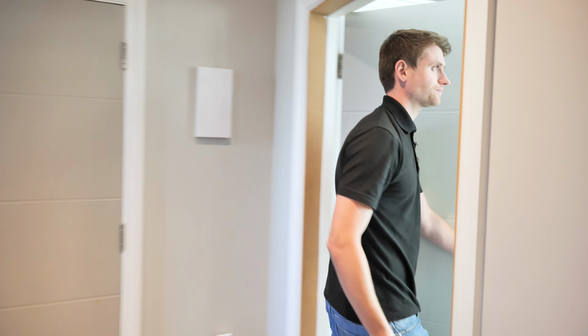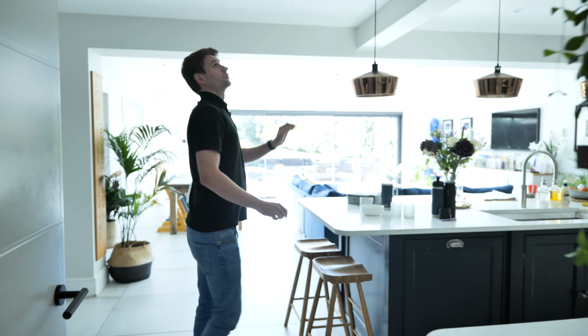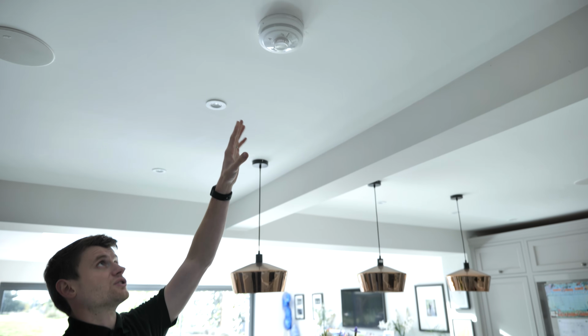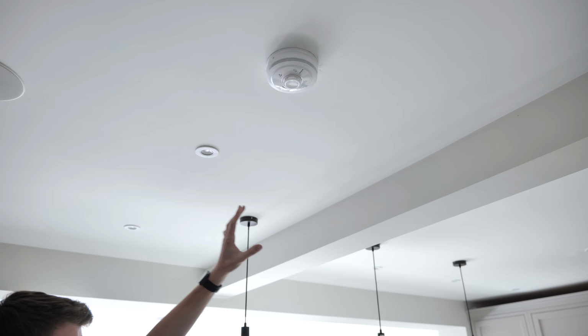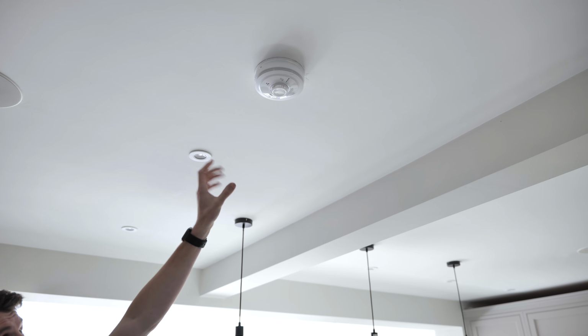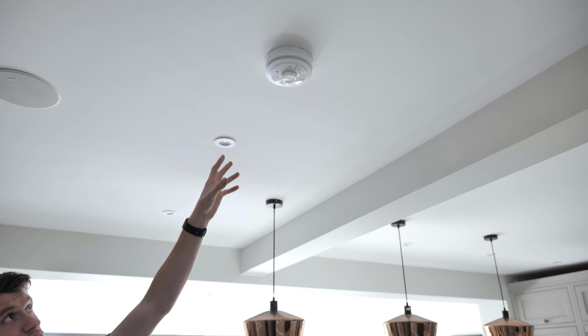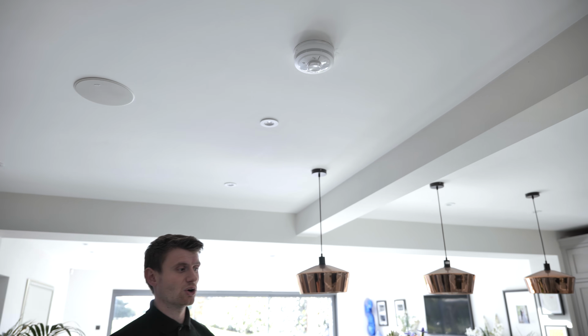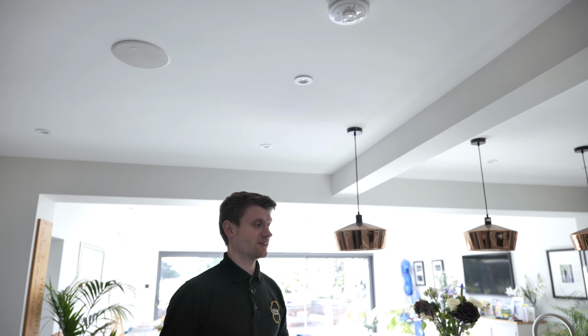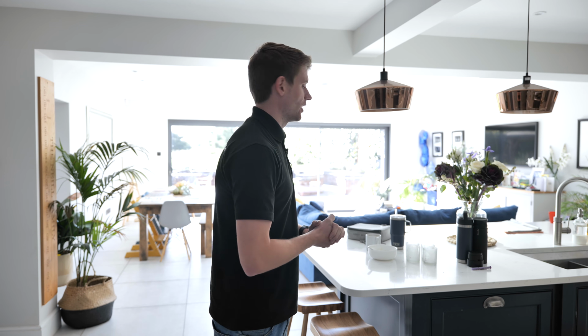If we come into the kitchen, so we've got a multi-sensor here, which has also got carbon monoxide, because we've got some gas appliances in and around here. So that's a multi-sensor again, so heat and smoke, but also the carbon monoxide. So even though it's heat and smoke, if you were to burn some toast, and the smoke alarm goes off, if it senses the smoke but not the rise in heat, then it won't go off. So that's why we like to use the multi-sensor ones, because it's like a dual. It prevents any kind of nuisance alarms, really. It looks for multiple different things happening within there.